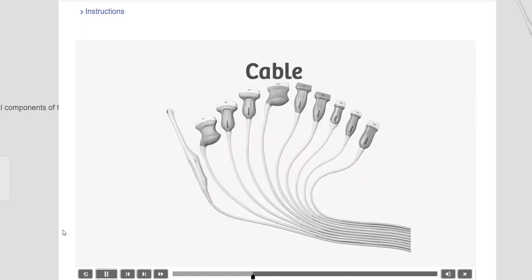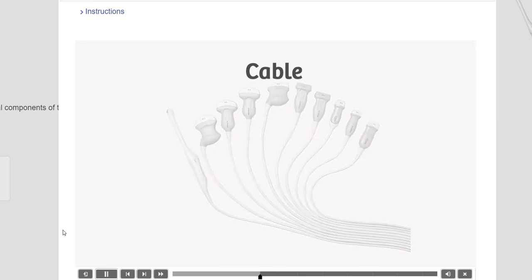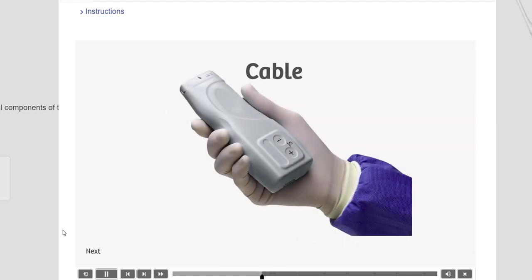The external cable material is lightweight and supple. Within the cable, there is power to the transducer and sophisticated wiring between the elements and the ultrasound system. Wireless transducers that do not have cables are available.